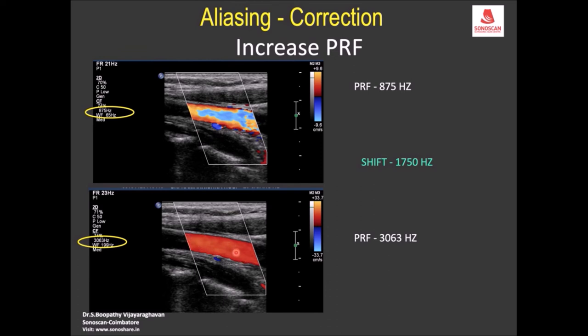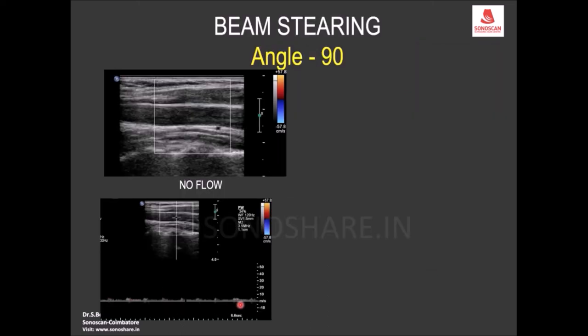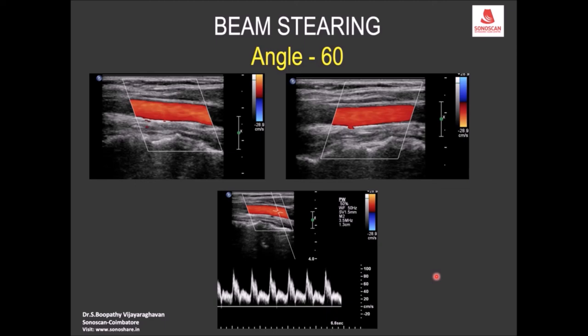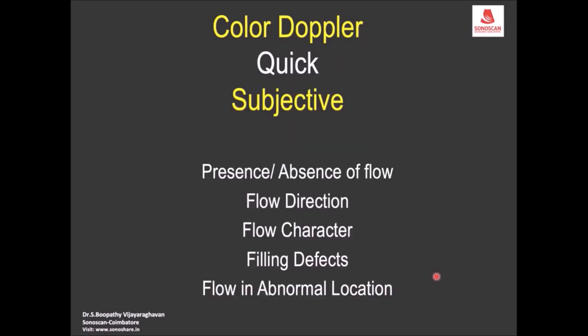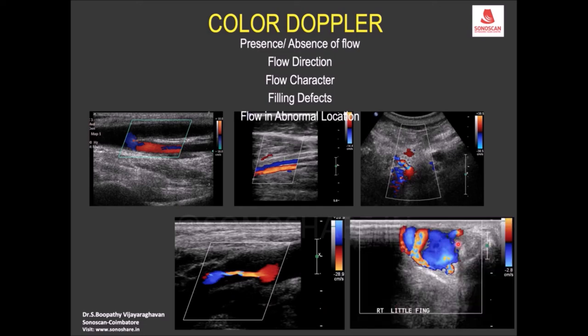Color priority settings control whether grayscale or color is given priority — with color priority, the grayscale is suppressed and color is displayed clearly. Beam steering must be used to give an appropriate angle relative to the blood flow direction. Frame rate and other parameters can all be analyzed together. The color box provides all flow information at once, and can reveal flow in abnormal locations such as in a pseudoaneurysm.